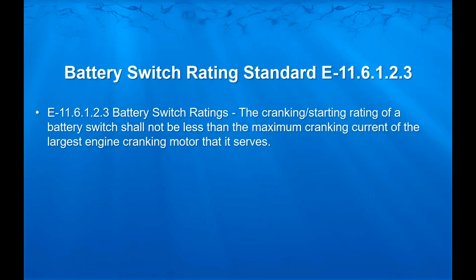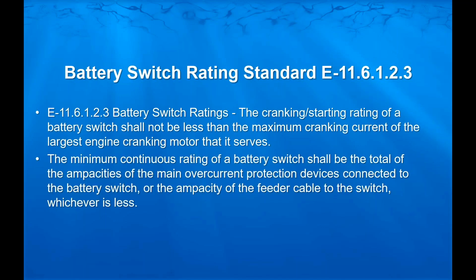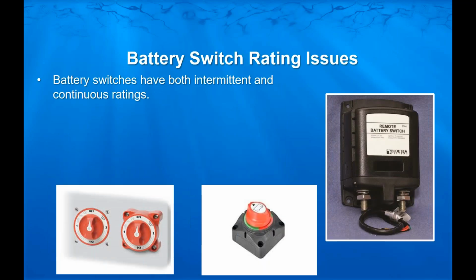So here we are at our ratings, which I mentioned earlier. The cranking starting rating of a battery switch shall not be less than the maximum cranking current of the largest engine cranking motor that it serves. The minimum continuous rating of the battery switch shall be the total of the ampacities of the main overcurrent protection devices connected to the battery switch. Means like our situation where you have one battery and overcurrent coming off and a circuit going to the panel or whatever else. That switch has got to be rated to handle the capacity of both of those, or the ampacity of the feeder cable to the switch, from the battery to the switch, whichever is less.